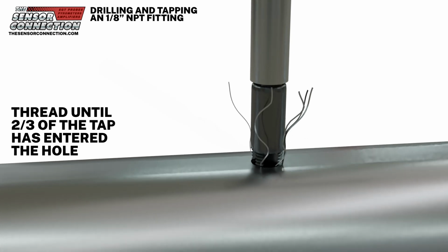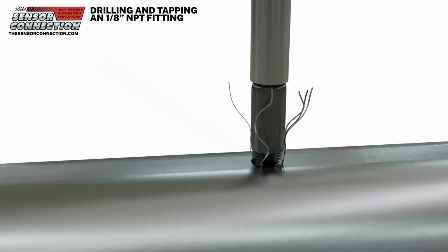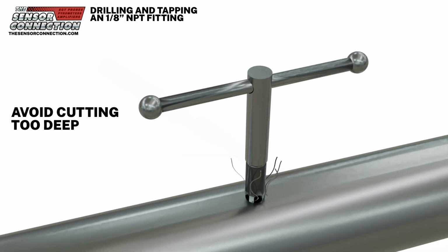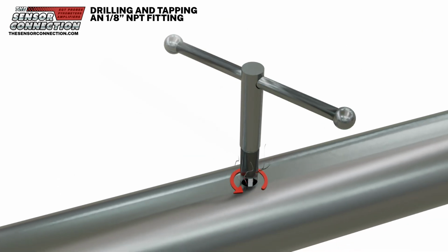Continue threading until about 2/3 of the tap's tapered section has entered the hole. Avoid cutting too deep. If the tap goes in too far, the threads may be oversized and the compression fitting might not form a proper seal once installed.